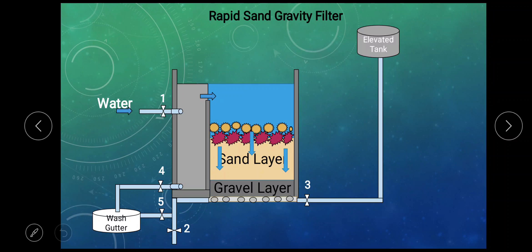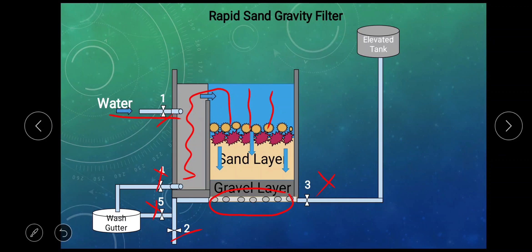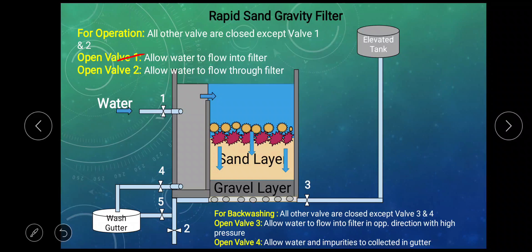This is the pictorial representation of rapid sand filter. During operation of rapid sand filter, only valve 1 and valve 2 are open and all other valves are closed. So water is injected from valve 1, which can percolate through the sand layer and is collected in the under drainage system. From the under drainage system, the filtered water may be extracted out from valve number 2. Valve 1 allows the water to flow into the filter. Valve 2 allows the water to flow out through the filter. As the operation proceeds, impurities may come up with the filter water, so it is very necessary to clean the filter at regular intervals.